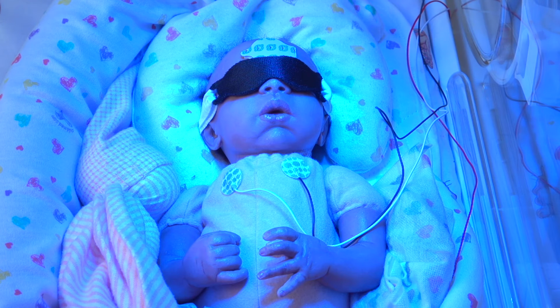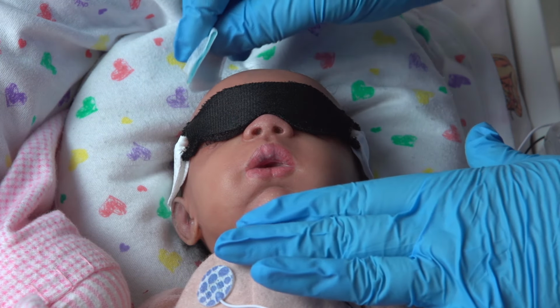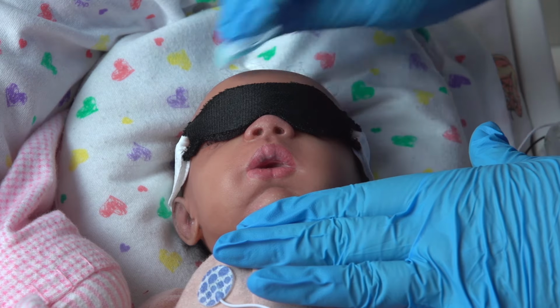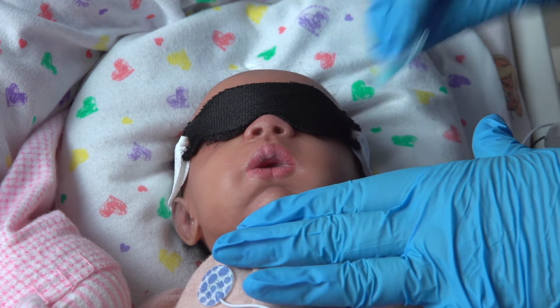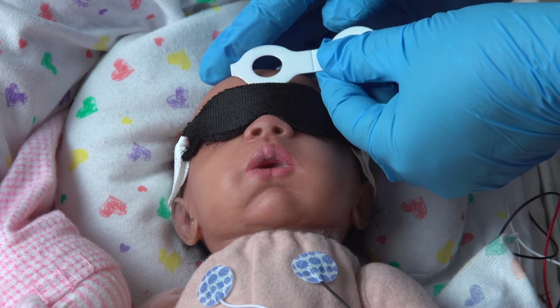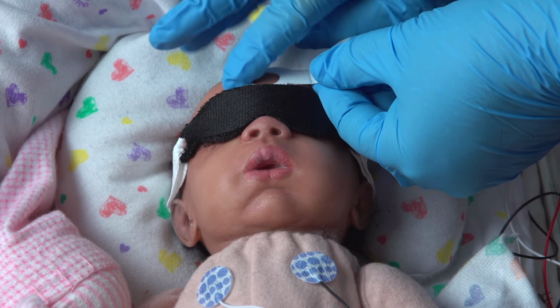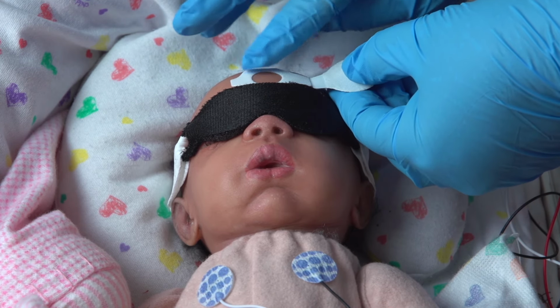During phototherapy, protecting the measurement site from phototherapy light using Biliclips phototherapy protective patch or adhesive skin patch is an important requirement. Before placing the Biliclips on the infant, always clean the skin site with a hospital-approved cleanser. Place the Biliclips patch over the measurement site prior to the start of phototherapy.